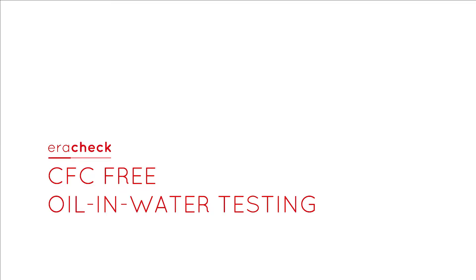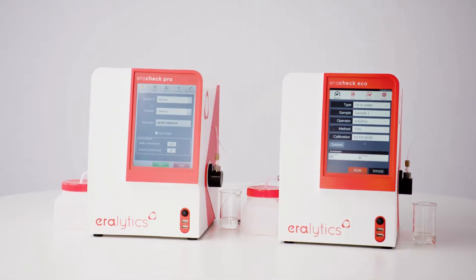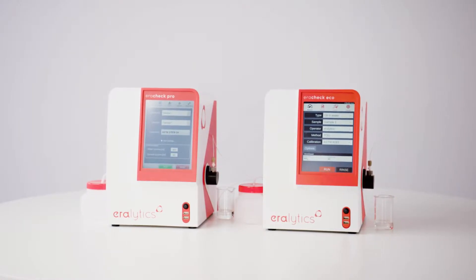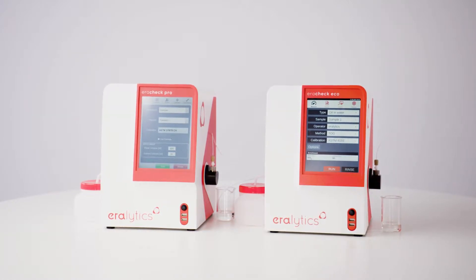Eracheck – CFC-Free Oil & Water Testing. Eracheck easily measures sub-PPM concentrations of oil in water using the CFC-free solvent cyclohexane for sample extraction. After extraction, the instrument determines the oil concentration by an IR measurement of the extract.